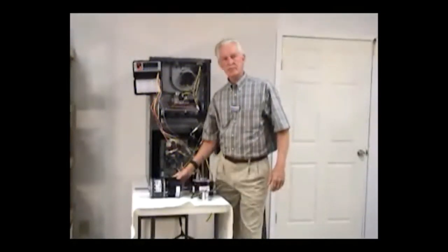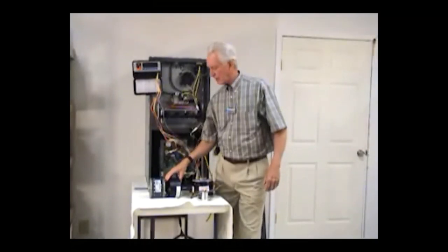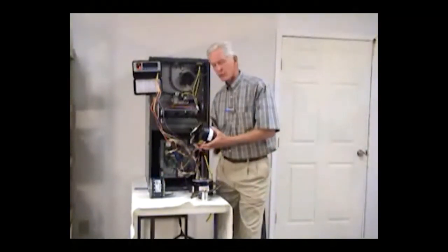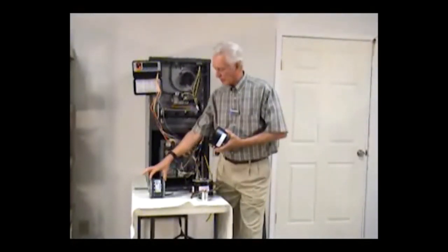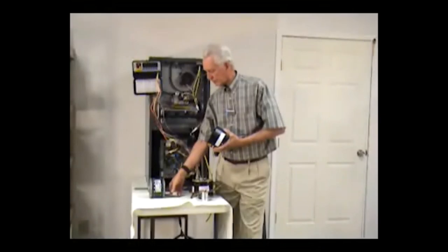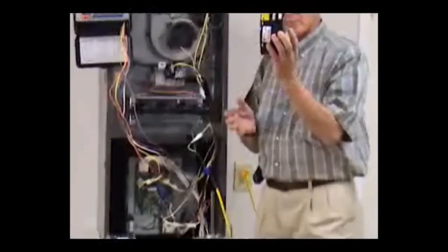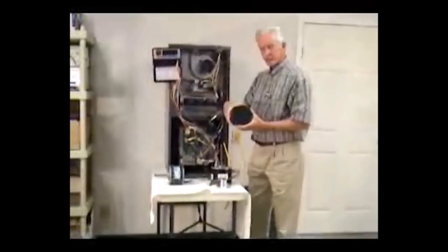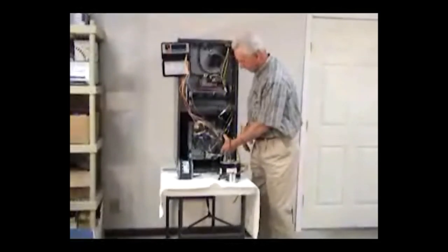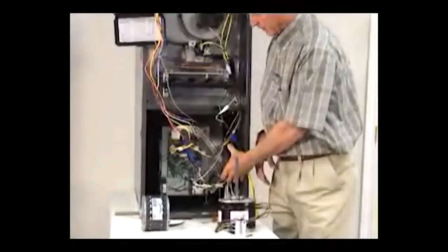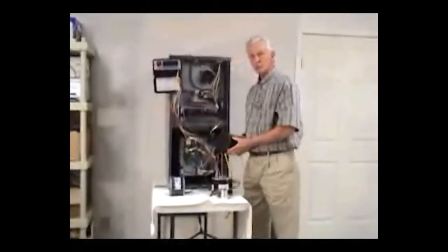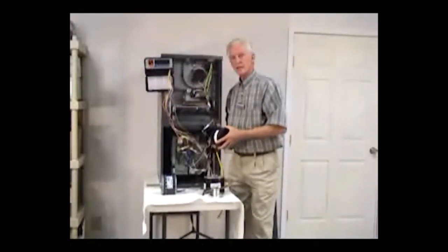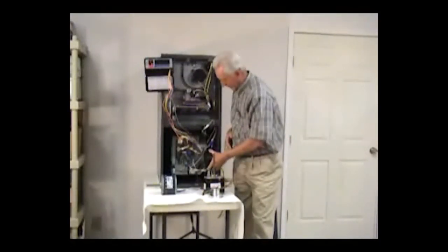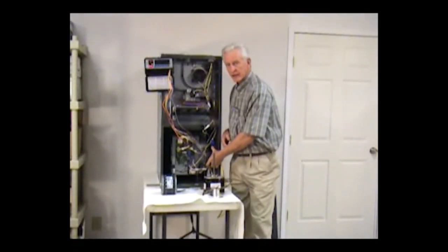Let's cover a little history on ECM motors, dating back to somewhere in the late 80s, early 90s. The original ones, which we don't have one here with us that we can show you, but I can give you a little demonstration as to how those were put together. The motor itself looked basically just exactly like this right here. The connector itself came from the motor to a module, which was not connected to the back of the motor, but in a square box form similar to this, attached to the inside of the air handler or the furnace. And then your electronics from your board would come to the square box, and that version of this motor was a 1.6 version. And again, it had the module attached inside of the air handler or the furnace.